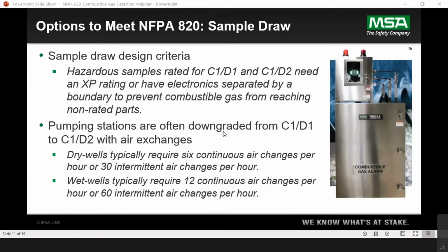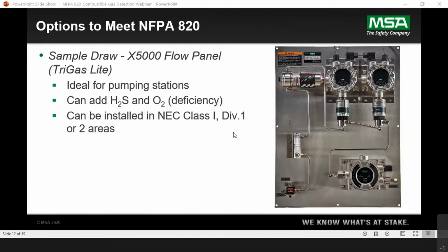But the important thing is, what is the criteria or classification of the sample when it's taken? So to meet 820, for pumping stations, we will use a flow panel. There's one there on the right. We mount all the sensors on a panel with tubing, a pump, a flow meter, and a 3-way valve for calibration. And we can add H2S and oxygen as needed. These can be installed in a Class 1, Division 1 or 2 area. So this flow panel, the Tri-Gas Lite, has the capability to go in either classification area, which makes it a really easy installation where you're not too concerned about which classification it is.